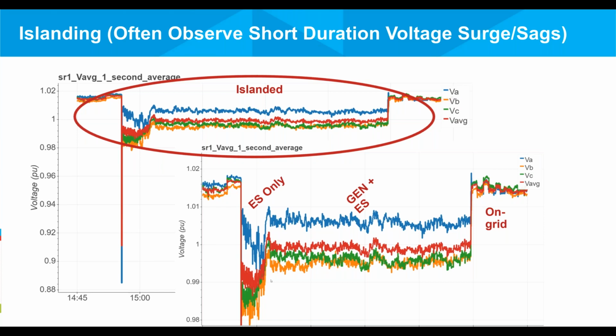The generator took some time to start up. But when it eventually started up, it picked up the load, and the generator and energy storage were operating simultaneously. But the generator was primarily the grid former. The generator provided the voltage and frequency regulation throughout the 1 hour that the microgrid picked up the load, and then after that hour, the smart homes were resynchronized with the grid.